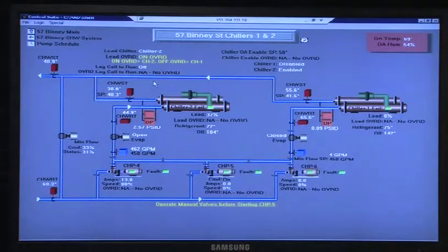That's why it's running. If you're looking at the system and you want another chiller to run, you can override that point on and it will bring the other chiller on. Are we going to get an alarm point that says this one's on, it's over 95% of the demand? You won't get an alarm for that. You'll get high chilled water temperature alarms, but not because it's over 95%.